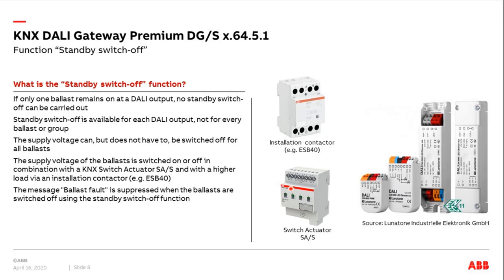What we need is an additional switch actuator to switch off the supply voltage. If you want to switch a higher load — not only 16 or 20 amps — we can control via a switch actuator an installation contactor with, for example, 40 or 63 amps, so we can switch off a very high load.